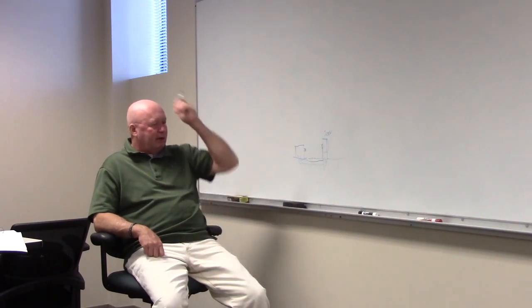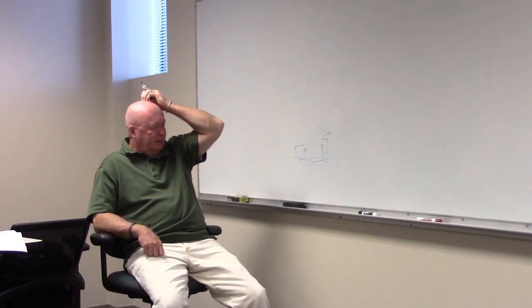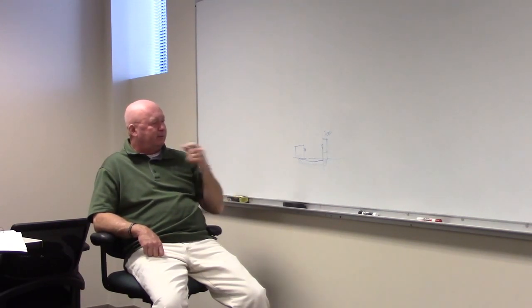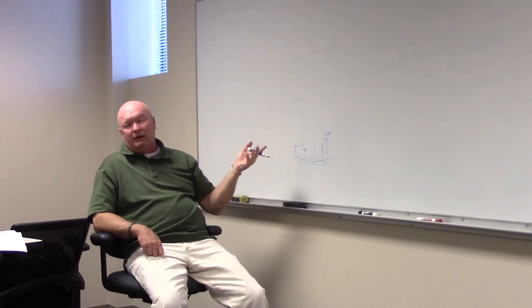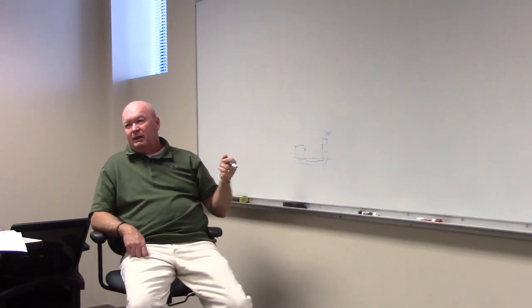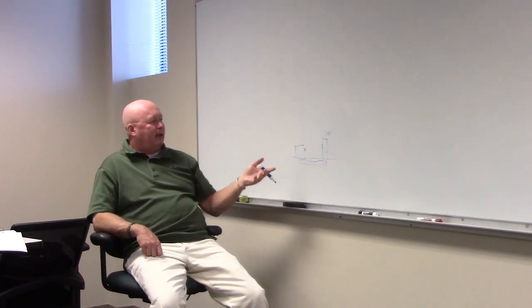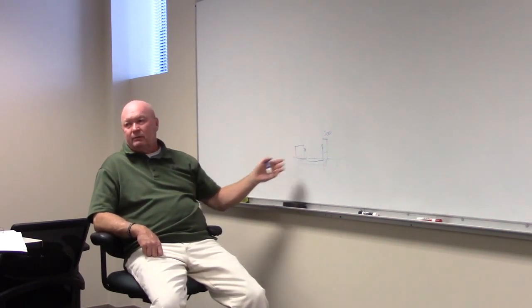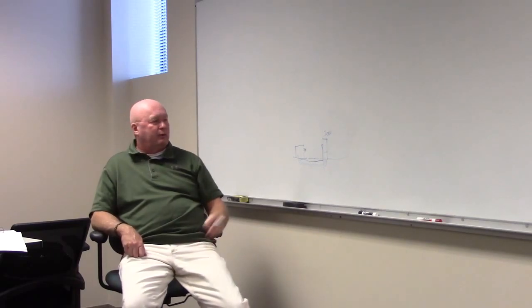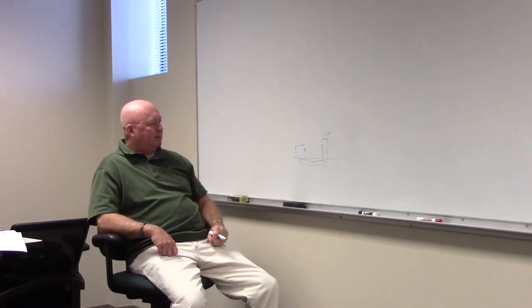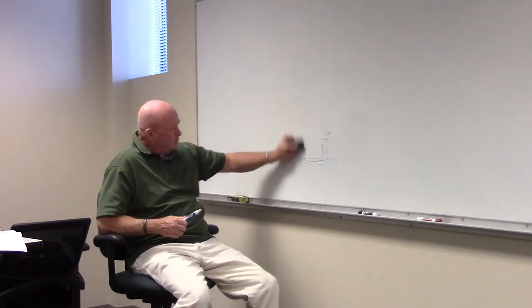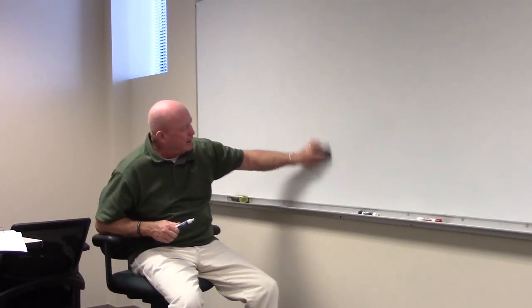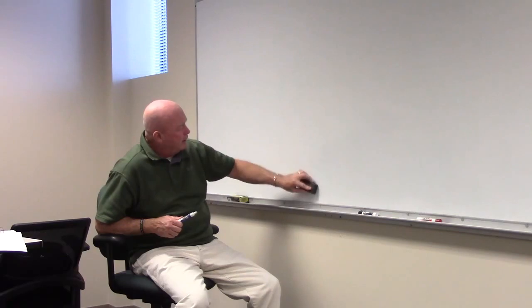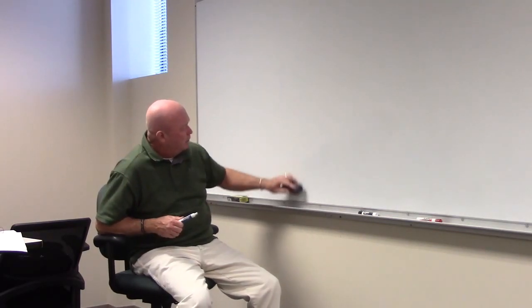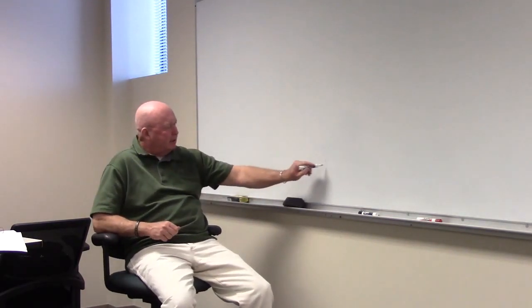Now, one thing's required, since there's no cutoff outside, the local fire marshal will probably require the building person, a commercial facility, to put something called a Knox box on the outside, which is the key to get into the building. They can cut the power off here, of course, and that's probably where they're gonna throw it in this situation, aren't they? But that's a designated area, usually within a room called the electrical room, isn't it? And we want to minimize this length from here to here.